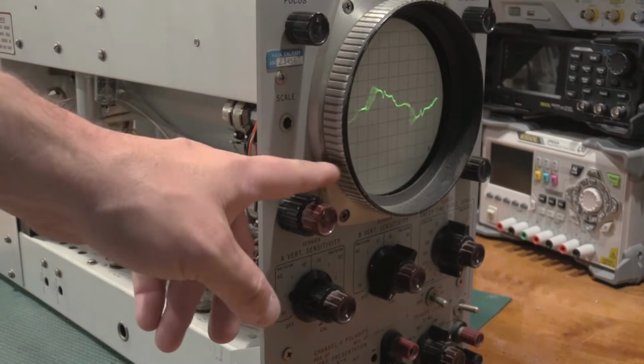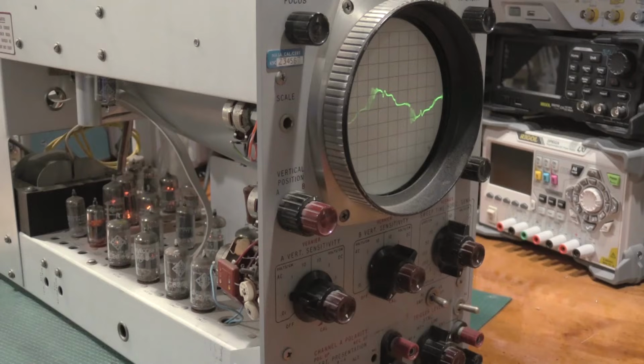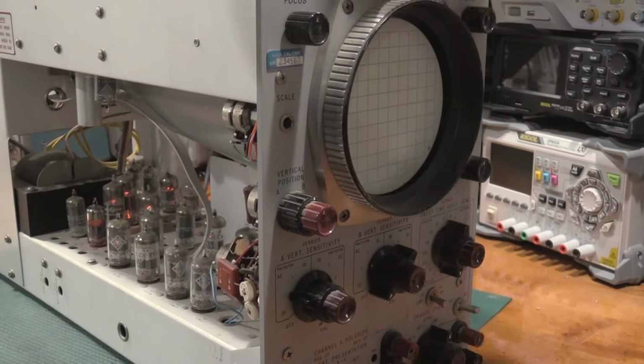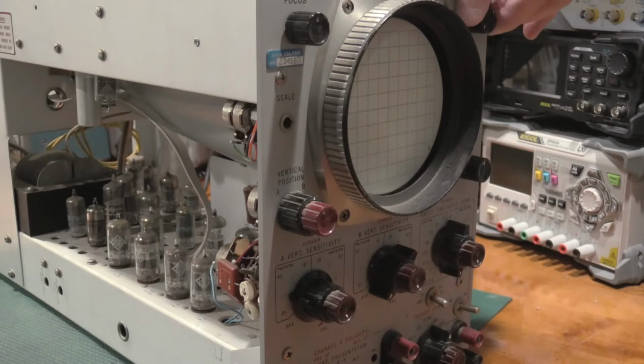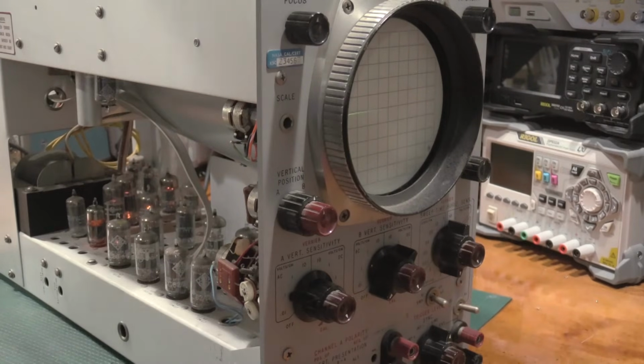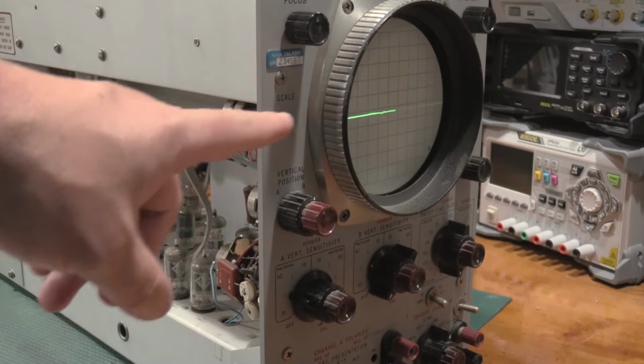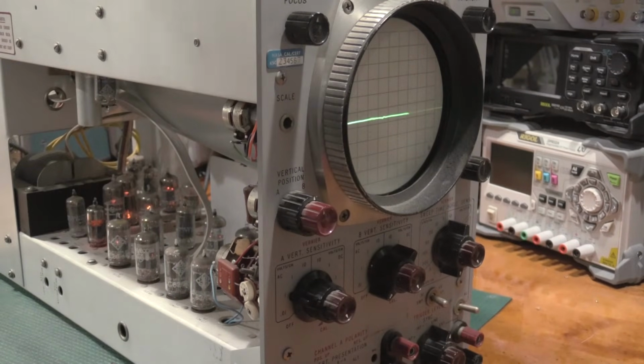The trace is scrambled right now because there is no ground reference, and the chassis is open, so it's picking up noise from everywhere in the lab. So let me get it off of the isolation transformer and onto a correct 3-pin outlet. We'll see if that noise goes away. Modern rooms are just horrific for noise. It's awful. Okay, here we go. 138 and there we go. Nice trace. All right. I'm going to shut this off now, get this repositioned safely, and then we'll throw some signals at it and see what happens.